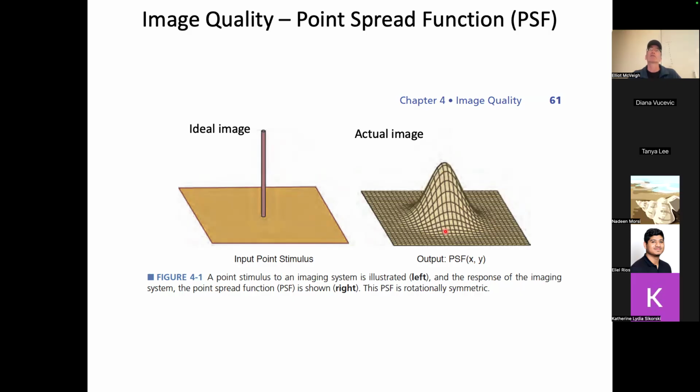For a CT scanner, the way we get a point spread function is we put an extremely fine metallic object in the scanner. So if we're just doing 2 dimensions, X and Y, we could take a wire that is some metal, and maybe it's 50 microns in diameter, right? So it's like a metallic line that's 50 microns in diameter. That's well below what the resolution of the scanner is, and it will produce a signal that looks like this. And you can measure the width of that signal.